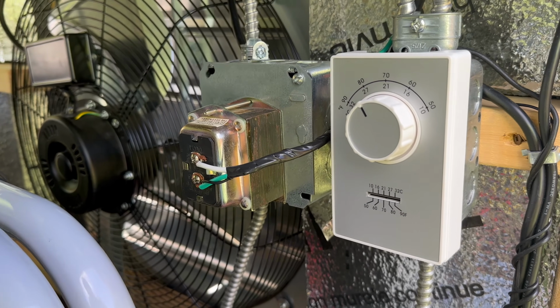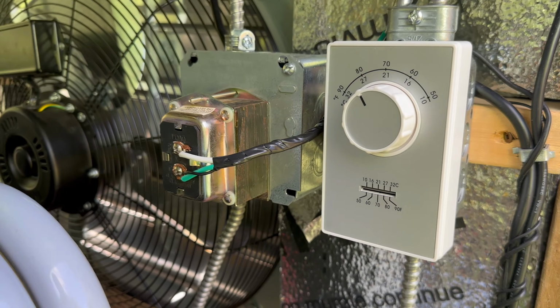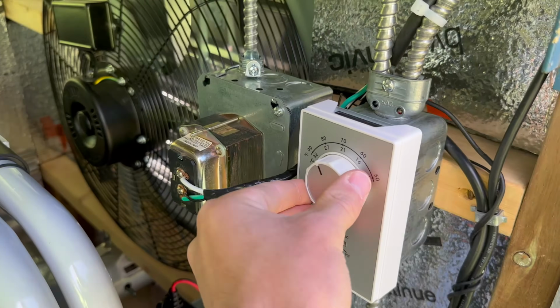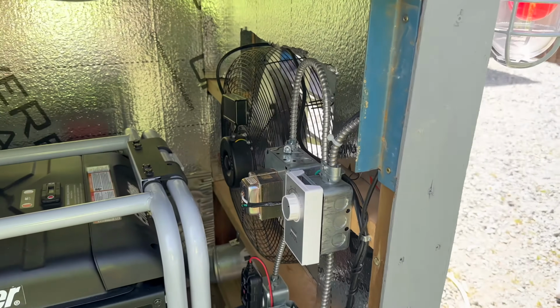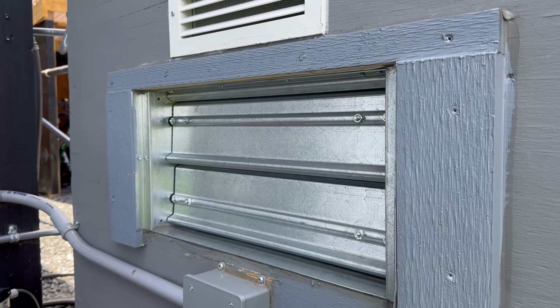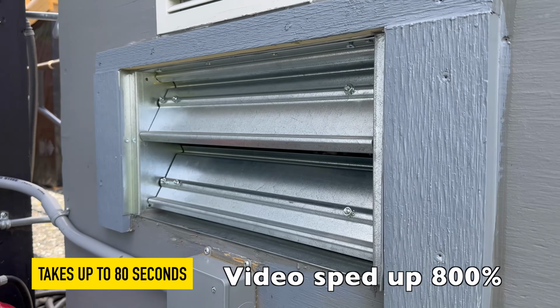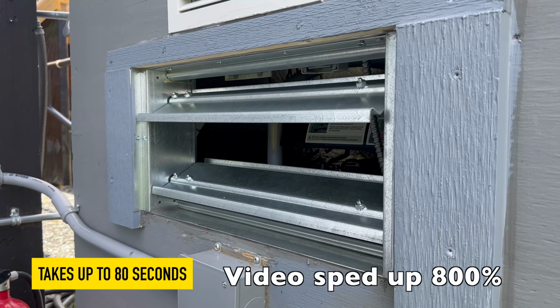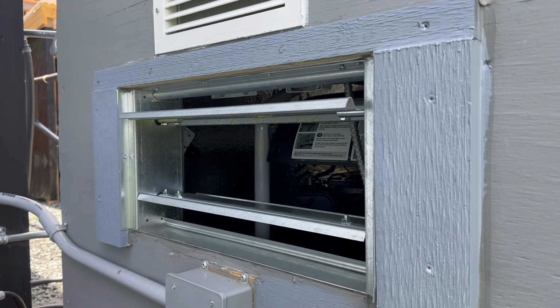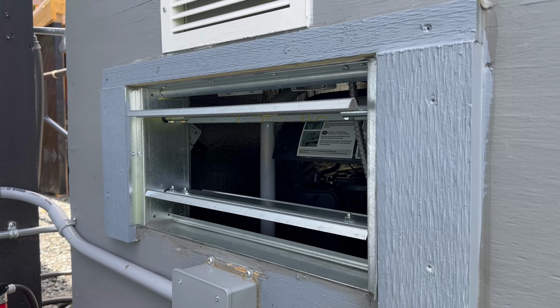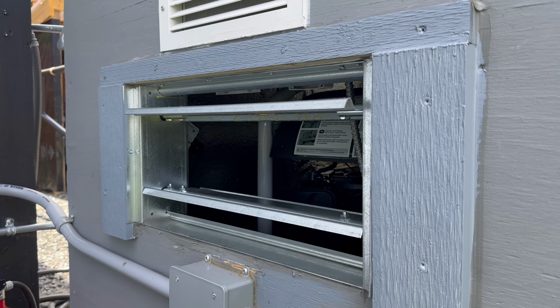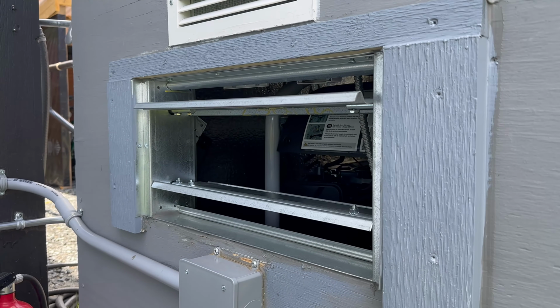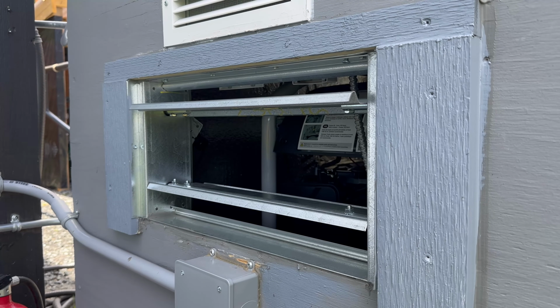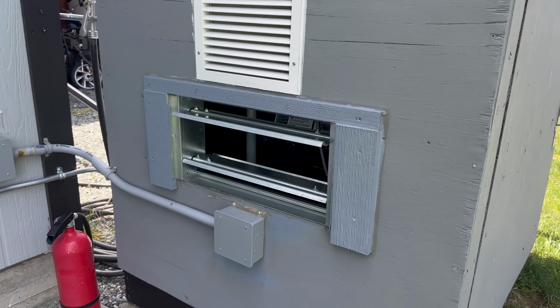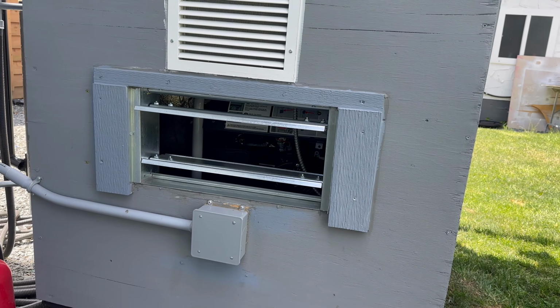I will demonstrate this now by turning the set point of this thermostat down to a lower temperature so the fan will turn on and the damper will open. That has the damper in the fully open position, so the damper is currently receiving 10 volts on the 1 wire as well as its normal 24 volts that it always has. Now once the 10 volts goes away and it only receives the 24 volts on the other 2 wires, it will go back to the fully closed position. This system draws around 3,000 CFM of airflow.